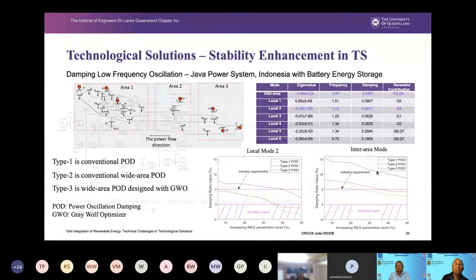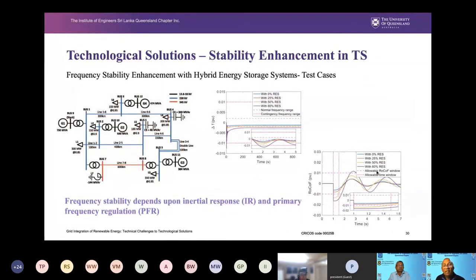The other case study we have is the frequency instability problem. What we found was that two factors are important: one is inertial response, the other is primary frequency regulation. These are some frequency traces for different penetrations of renewable energy. As you can see, 25% and 50% are okay, still within the margin, but 60% creates a problem. The bottom graph shows the rate of change of frequency curve, which is going to an unacceptable level. So we have to do something about it.